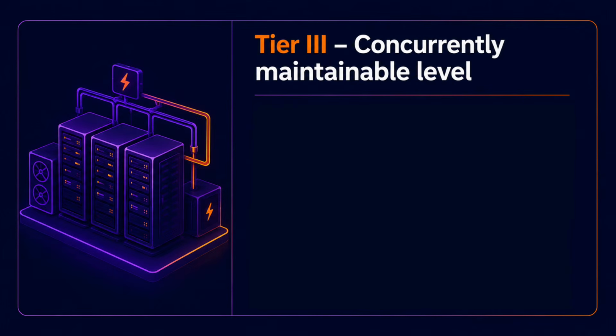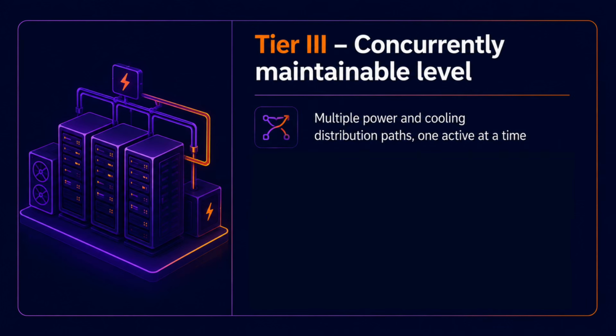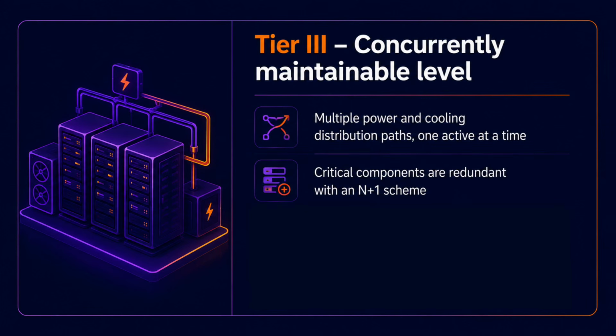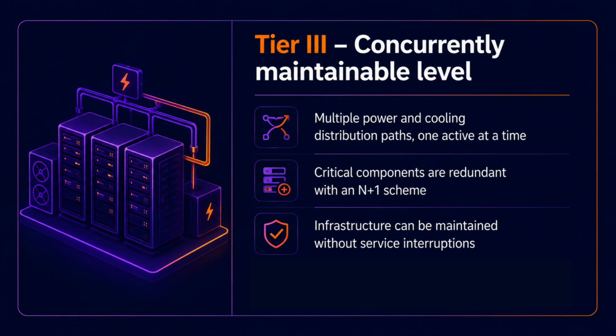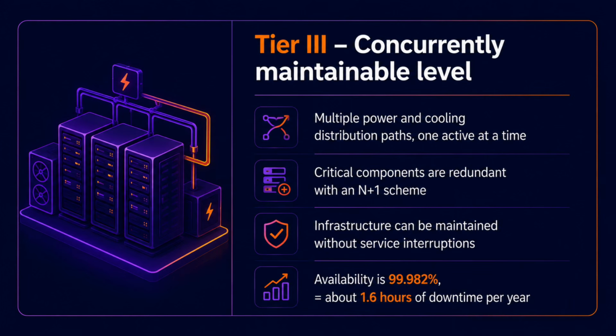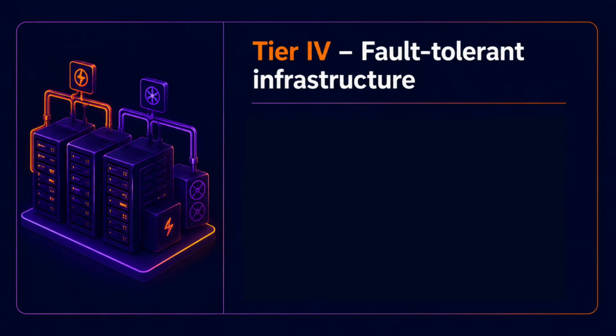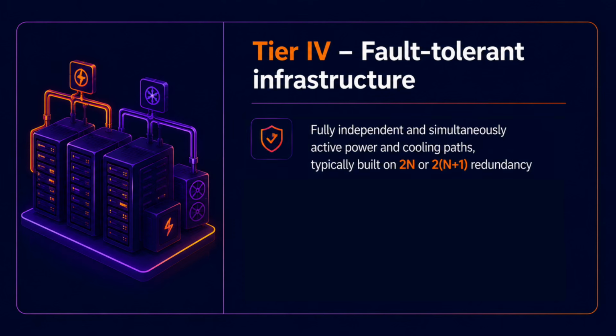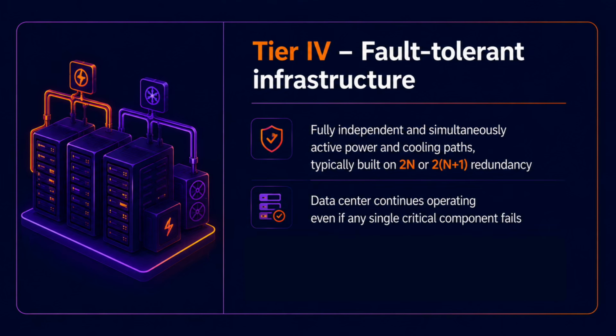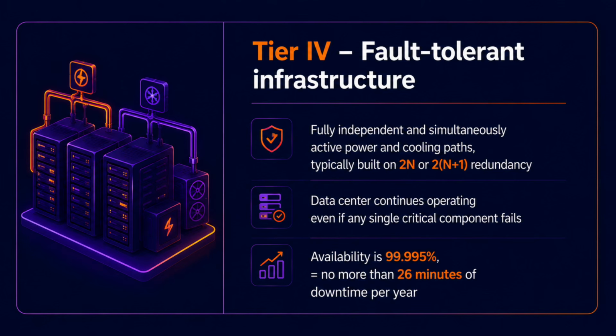Tier 3, concurrently maintainable level, provides multiple power and cooling distribution paths, with one active at a time. Critical components are redundant using an N+1 scheme. The key advantage is that infrastructure can be maintained without service interruptions. Availability is 99.982%, or about 1.6 hours of downtime per year. Tier 4, fault-tolerant infrastructure: fully independent and simultaneously active power and cooling paths, typically built on 2N or 2N+1 redundancy. The data center continues operating even if any single critical component fails. Availability is 99.995%, with no more than 26 minutes of downtime per year.